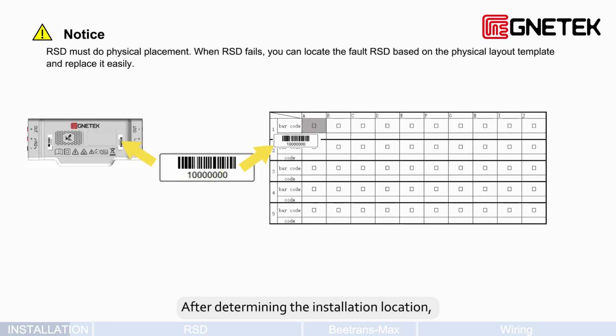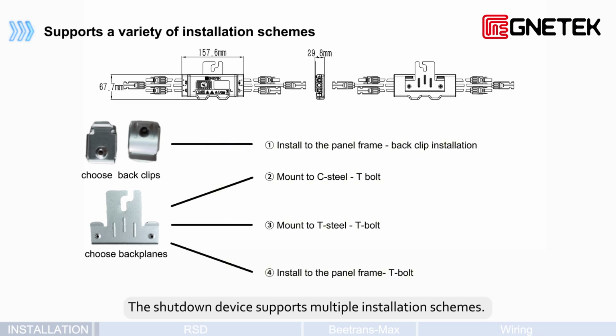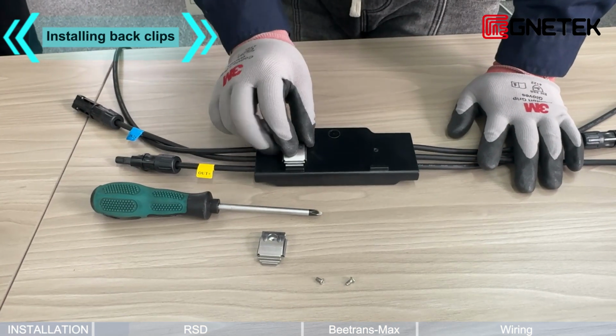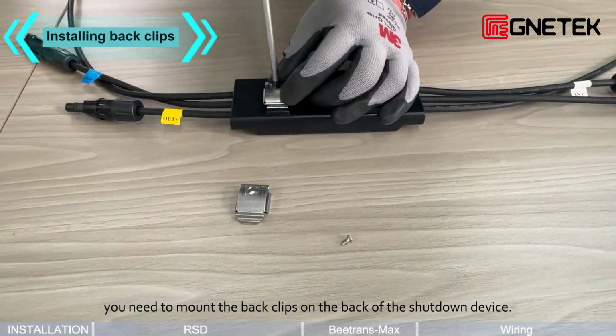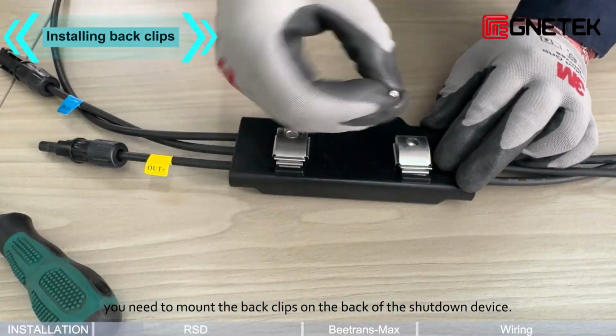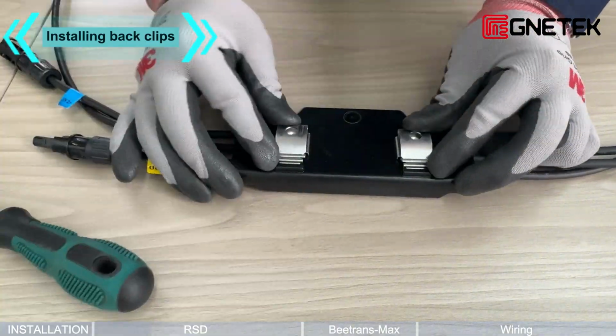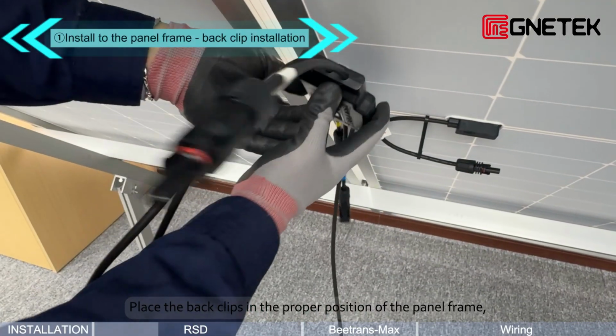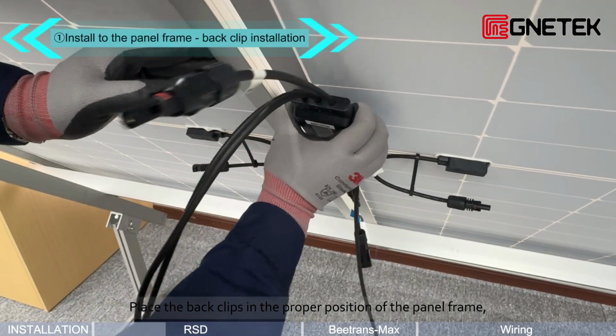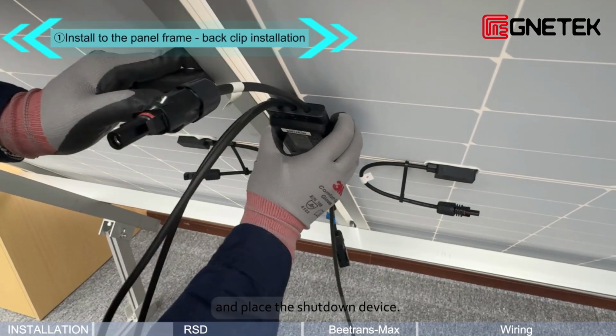After determining the installation location, remove the SN label from the shutdown device and stick it on the physical layout template. The shutdown device supports multiple installation schemes. Select an appropriate installation scheme based on the actual situation. After selecting the back clips, you need to mount the back clips on the back of the shutdown device. Place the back clips in the proper position of the panel frame and place the shutdown device.